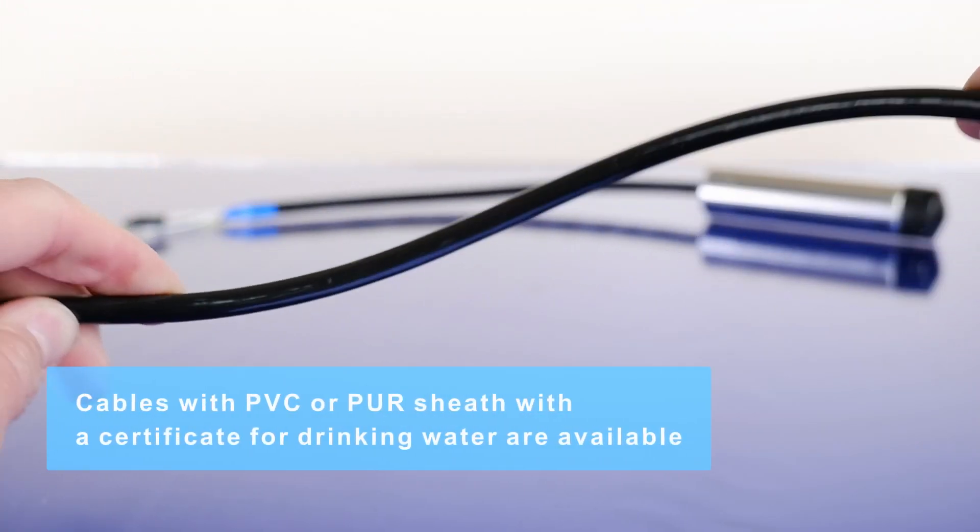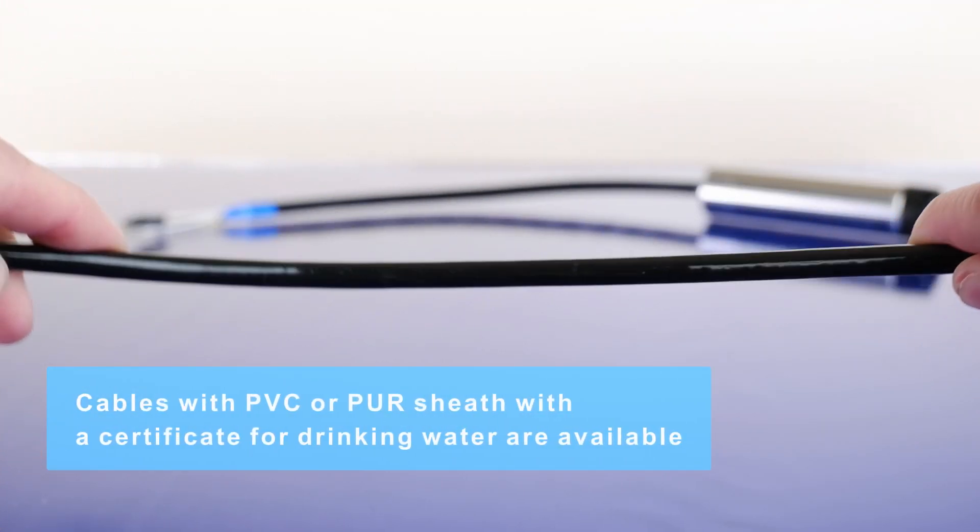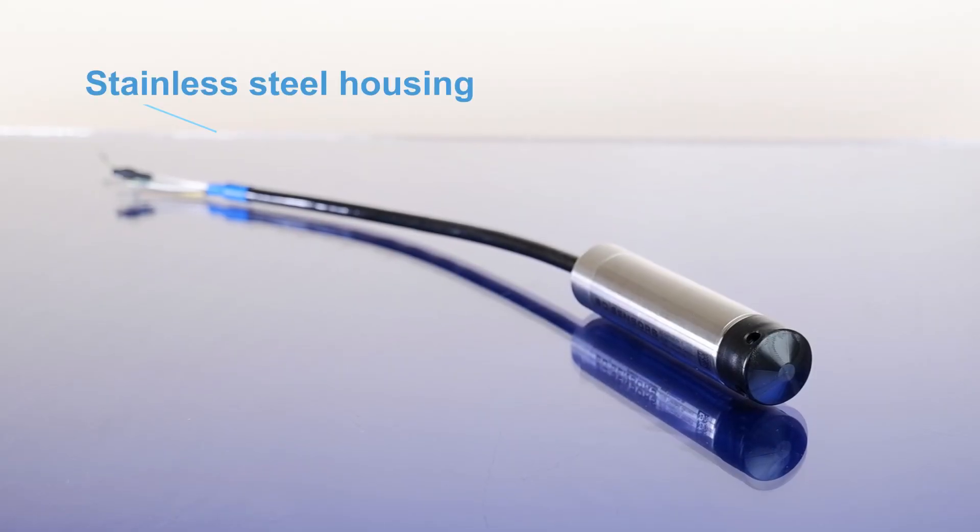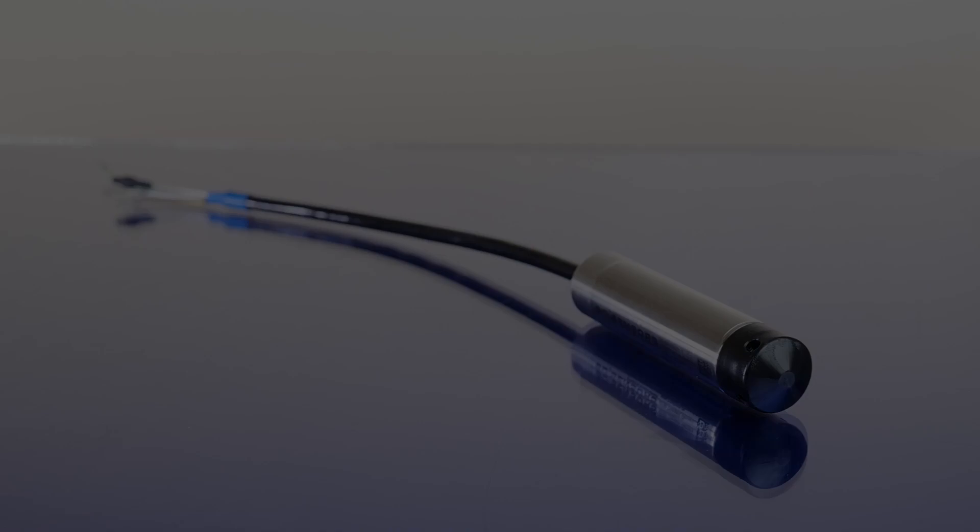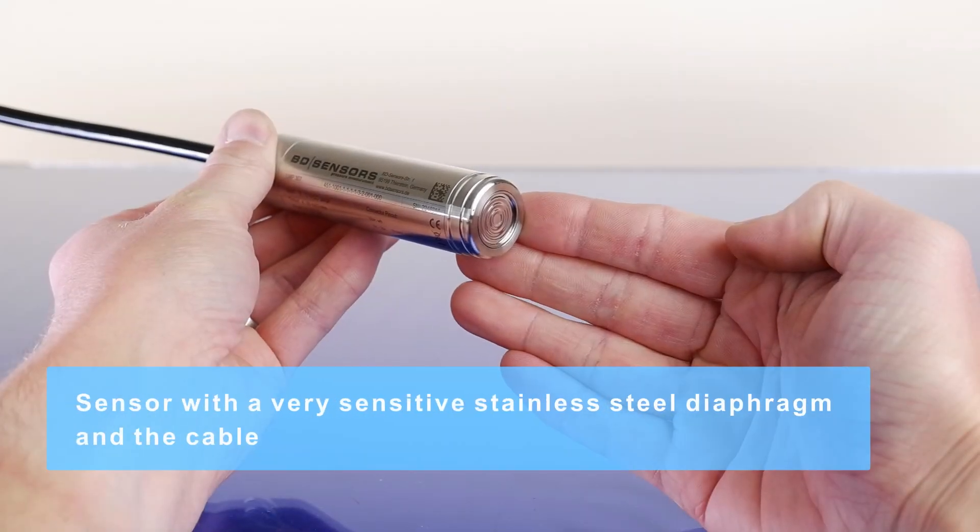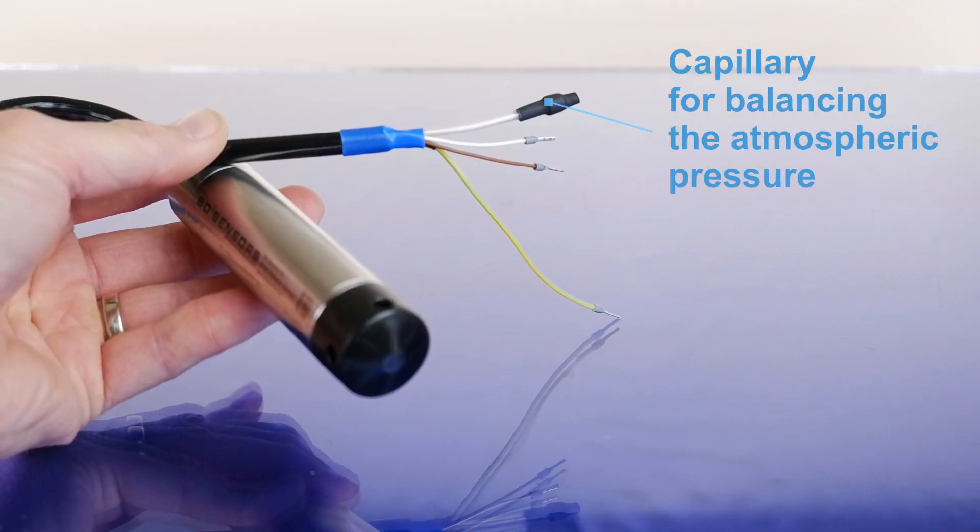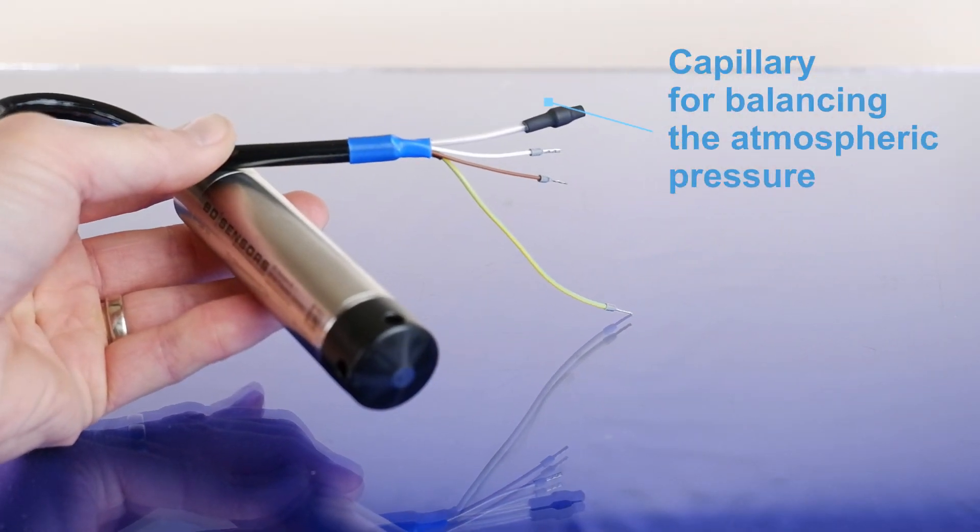Cables with PVC or PUR sheath with a certificate for drinking water are available. The probe consists of a stainless steel housing, plastic cap, sensor with a very sensitive stainless steel diaphragm, and the cable. The cable includes a capillary for balancing the atmospheric pressure.